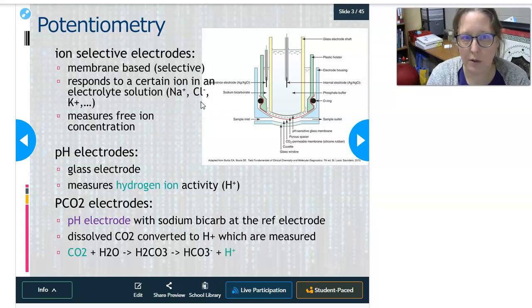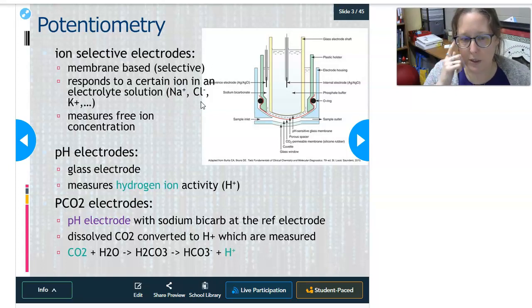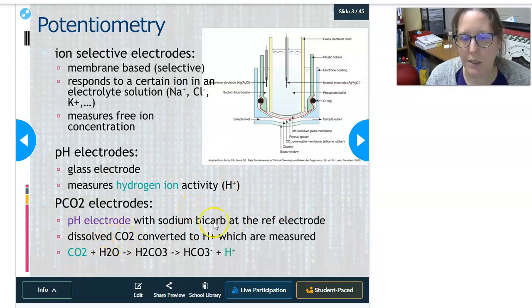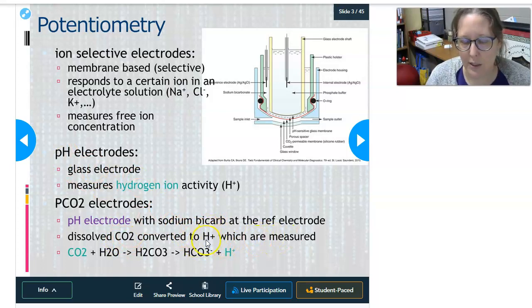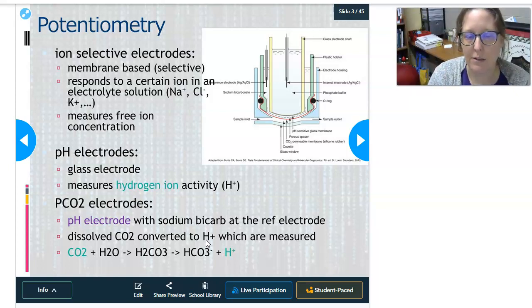pH electrodes are another type of potentiometry. They are a glass electrode, and the ion measured is the hydrogen ion, whose activity is converted into a specific pH. The pCO2 electrode is basically a pH electrode with sodium bicarbonate at the reference electrode. The dissolved CO2 is converted to hydrogen ions, which the pH electrode measures. For every CO2 molecule, there's a hydrogen ion made — a one-to-one relationship. So if you can measure the hydrogen ion concentration, you can deduce the CO2 concentration.